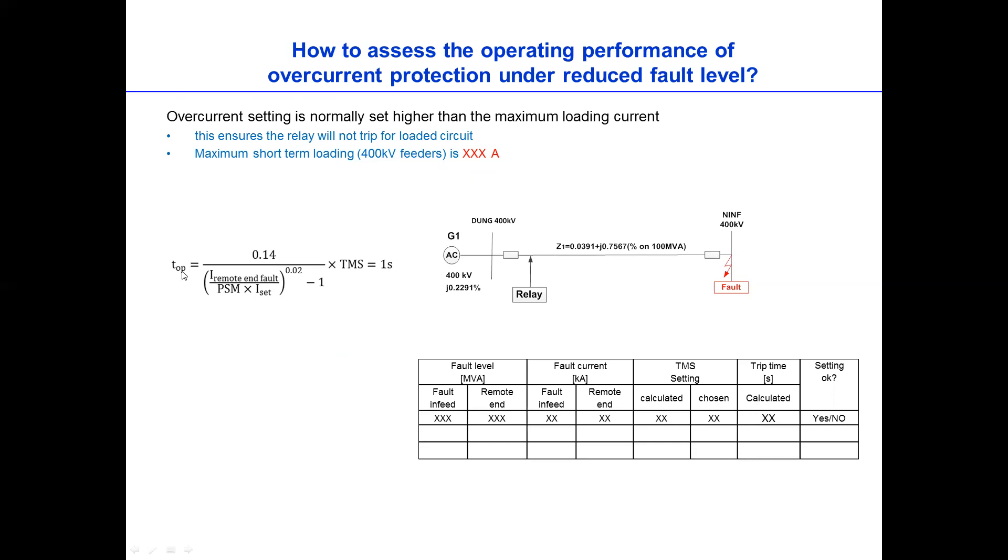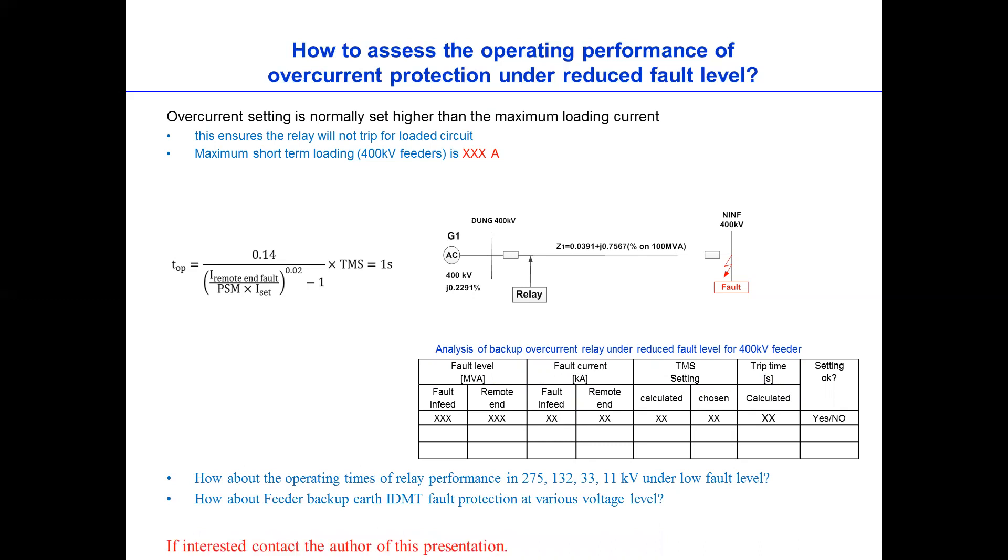So say we have 400 kV and then we have fault at the remote end. Then how do we calculate, say for example, maximum short term loading for 400 kV feeder is x amp or kilo amp. So we can calculate, of course, operating trip time of the relay using this formula. So let's say if at strong fault level, the trip time is one second because the generator is strong, how about if we reduce this fault level? So for example, if we reduce this fault level from the generator, how do we calculate? Do we first calculate the TMS? Or how about the trip time? So will the setting be okay? Yes or no? How do we assess? And then how about the operating time of the relay at different voltage levels and the varying fault level? And of course, how about the overall protection at various voltage levels? If you're interested to know or to learn more about this, well, please do contact me.